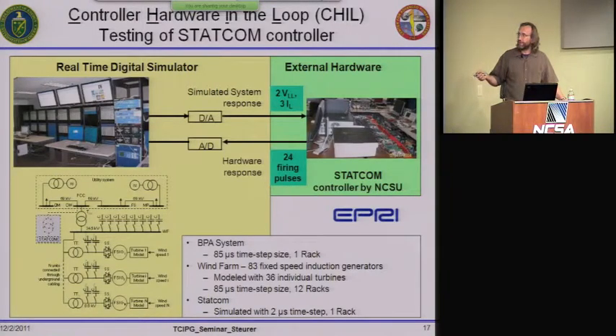We simulated all 24 power electronic switches, and we simulated the wind farm in relatively high detail since we had enough racks. We wanted to see how important it is to model a relatively high number of wind turbines versus lumping them together into one or two machines, and there were some interesting effects from that, along with local capacitor banks that had to be switched on and off.